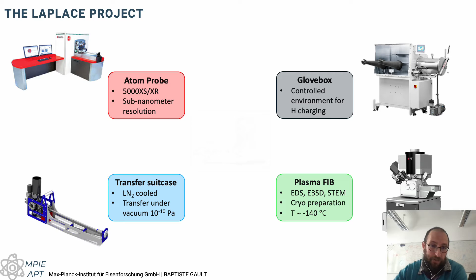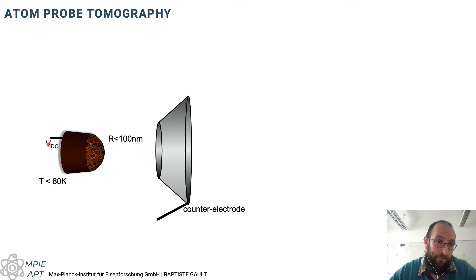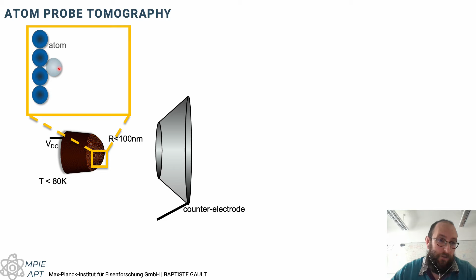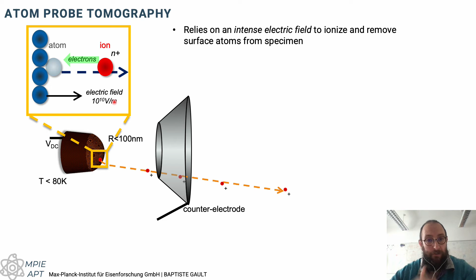So just as part of the introduction, what is atom probe tomography? Atom probe tomography is a microscopy and microanalysis technique. It makes use of a very sharp needle-shaped specimen, at the apex of which, when we apply a high voltage, a high field is generated. The field, when it reaches 10 to the 10 volts per meter roughly, starts to transform these surface atoms into ions, which are accelerated by the field, projected away from the needle, and fly along trajectories that are well determined based on the distribution of the electrostatic potential in the chamber.